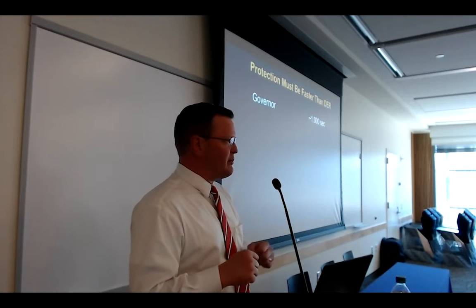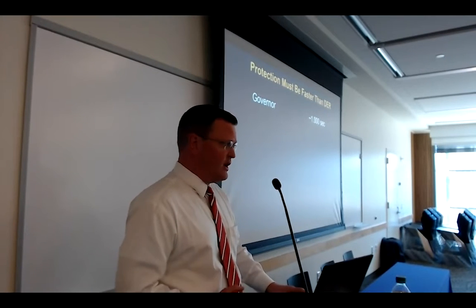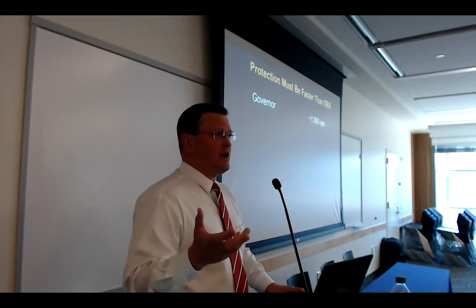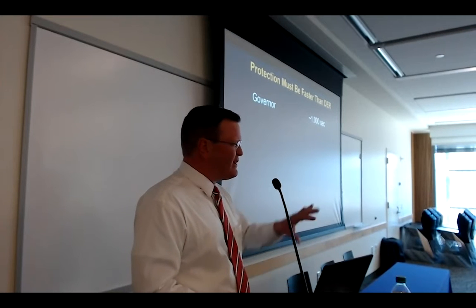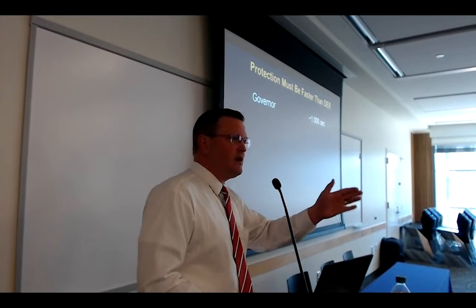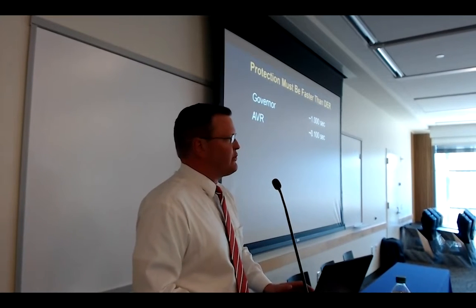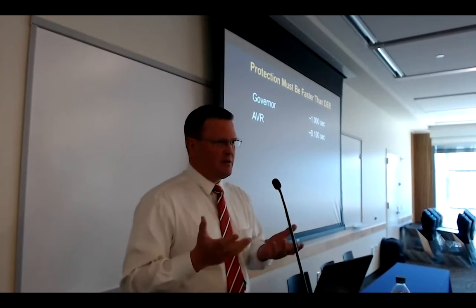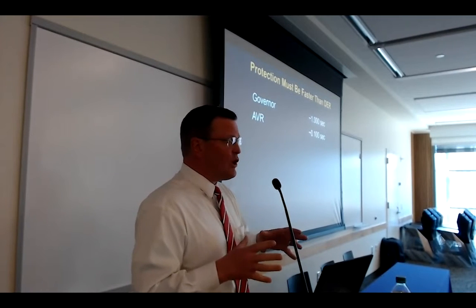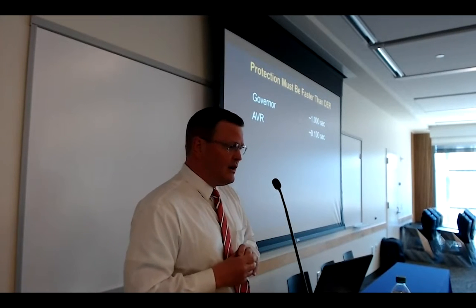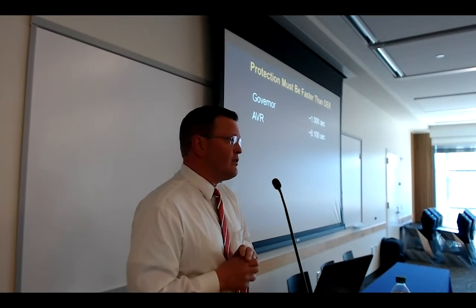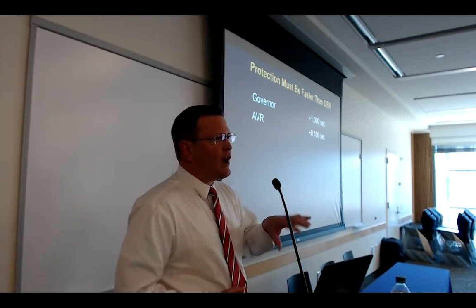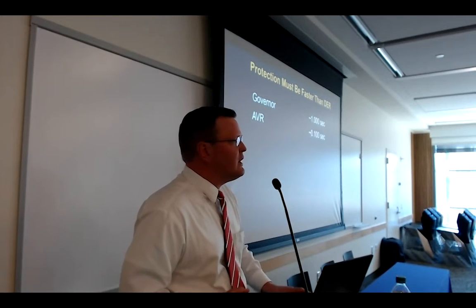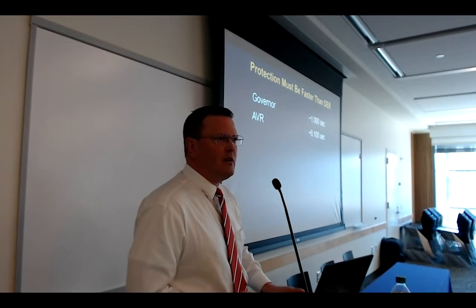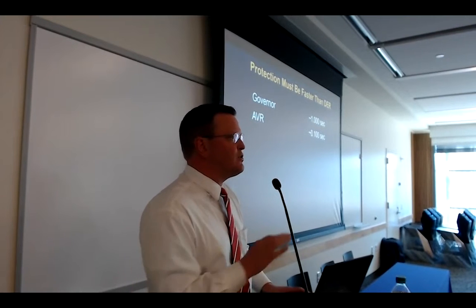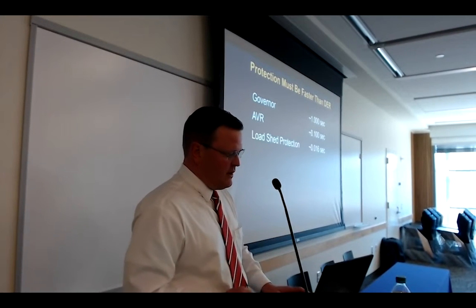Governors, fuel governors, whether diesel, a large valve for a steam turbine, or a gas turbine, have about a 1 second time constant. You can do better or worse. Automatic voltage regulators are basically DC drives that inject current into the field of a synchronous generator. They have a response time, depending on the L over R time constant, of about a tenth of a second. I'm throwing out orders of magnitude so we can get some relevancy.